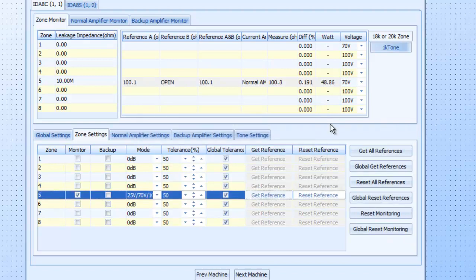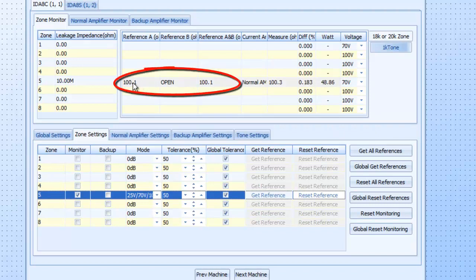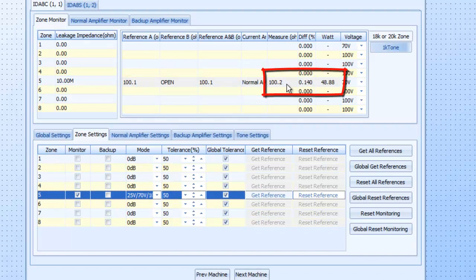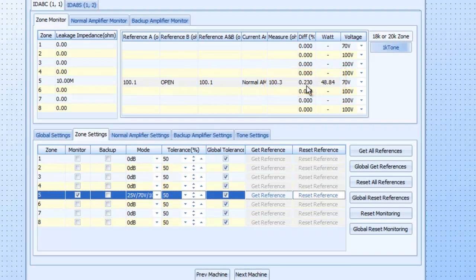And it goes back out and gets the new reference. Once you do this, this is the measurement that it's reading against all the time. And you can actually see the differences. And this is what it's currently measuring live. And you can watch it and see it's right at 100.3, 100.2, 100.1. The difference is 0.21. The minute this goes over your tolerance, that is where you're going to get your line error.